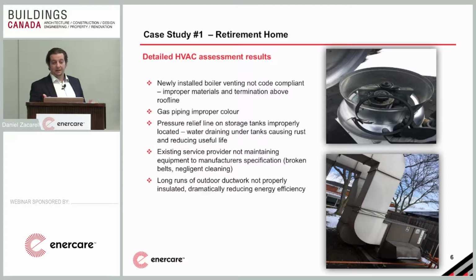It will start rusting through, cutting your storage tank life in half again, and as it rusts, a little pinhole leak happens, and with the amount - like 200 gallons of water, heavy - a pinhole leak turns into a leak the size of your face very quickly. It floods your boiler room, raises insurance costs, cuts off hot water and heat to your tenants, whatever it may be. So thinking about little things like that, having someone helping you with them helps you stay away from these issues to the best of your abilities.